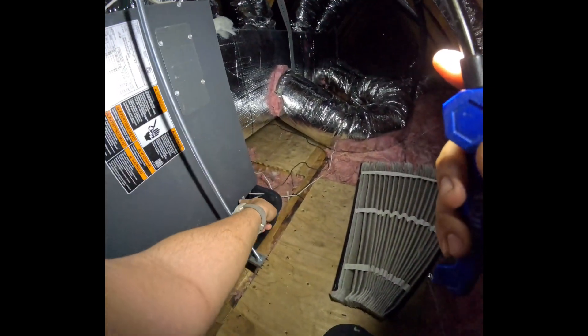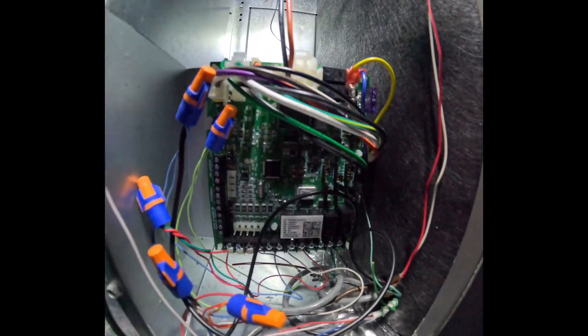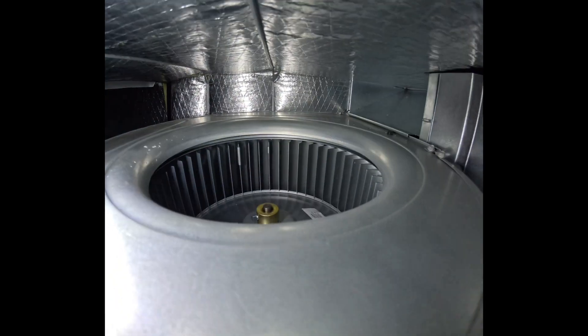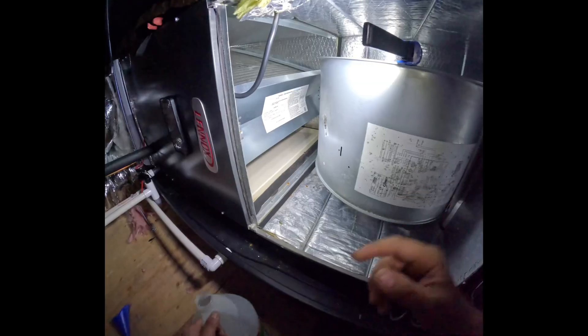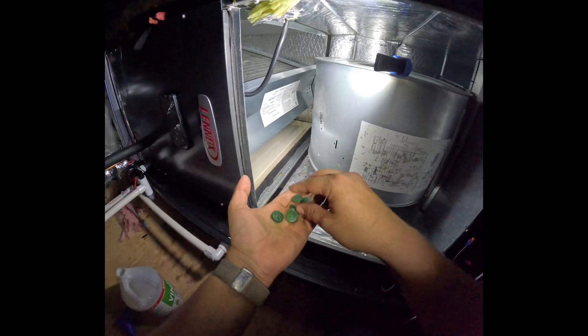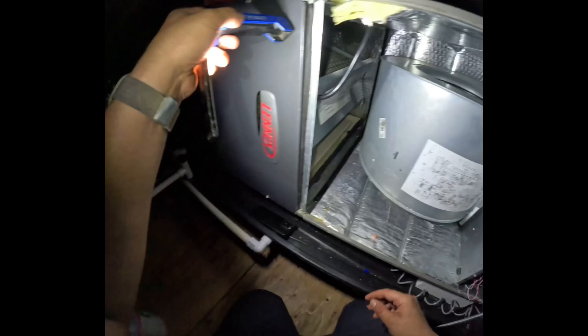It's time to go into the air handler by removing the four screws that hold the cover in place. We'll inspect the circuit board for burn marks, check the blower wheel for dirt and grime, and inspect the indoor coil. We'll look at the pan to make sure it's clean and check the blower motor, then flush the condensate pan to watch the drain flow and add condensate tablets to keep it clean. Let's get the P-trap cleared and then close the system back up.